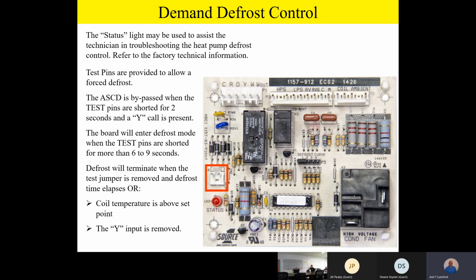So from a troubleshooting standpoint, watch this. If I jumper those pins, say for 10 seconds, and I go into a defrost, and let's say the outdoor coil is just packed full of ice, and I remove my jumper and it instantly jumps out of defrost, even though the outdoor coil is packed full of ice, I've got a bad coil sensor. Because remember, once you remove the jumper from those pins, it starts looking at the coil sensor for our 55-degree termination temperature on the coil. And so that's an important little troubleshooting tip.